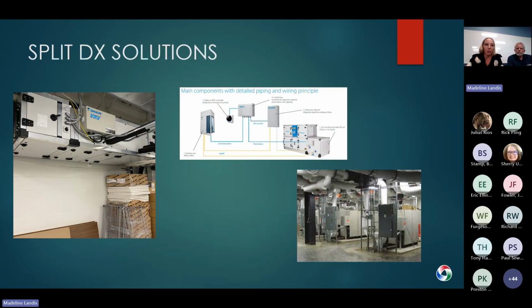And I think probably the most prevalent issue that we've experienced here at Long, or at least I have, is when you're using split DX retrofits or new installations. I think the first step is to confirm that the equipment is UL listed. Like Mark mentioned, typically the DX condensing units aren't the problem, but where you want to pay close attention is when you're selecting UL listed air handling units with those integral A2L refrigerant detection systems and coils.